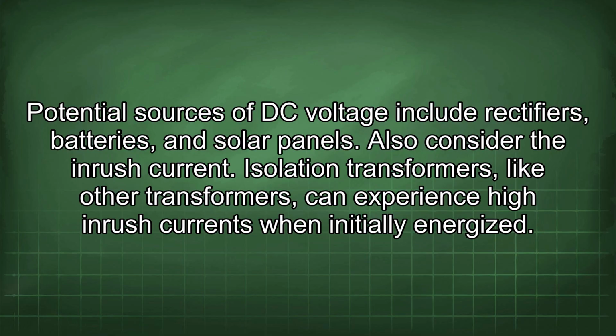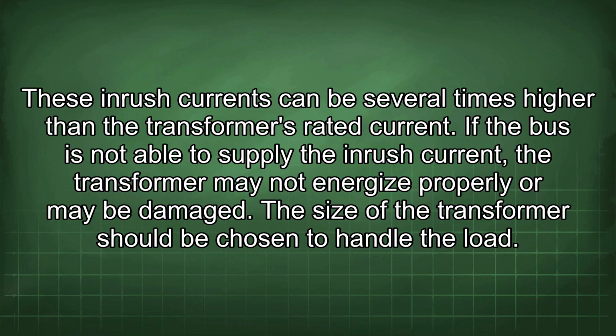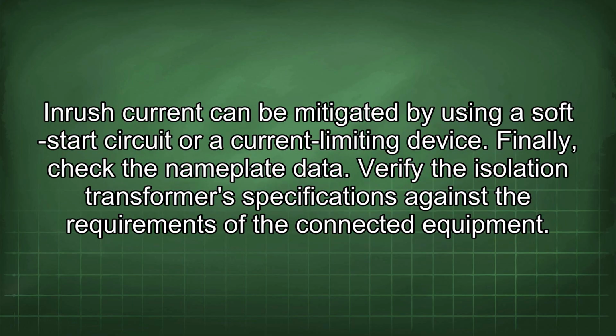Also consider the inrush current. Isolation transformers, like other transformers, can experience high inrush currents when initially energized. These inrush currents can be several times higher than the transformer's rated current. If the bus is not able to supply the inrush current, the transformer may not energize properly or may be damaged. The size of the transformer should be chosen to handle the load. Inrush current can be mitigated by using a soft start circuit or a current limiting device.